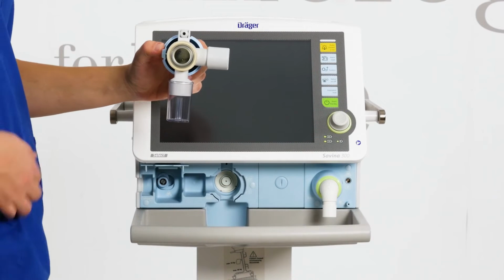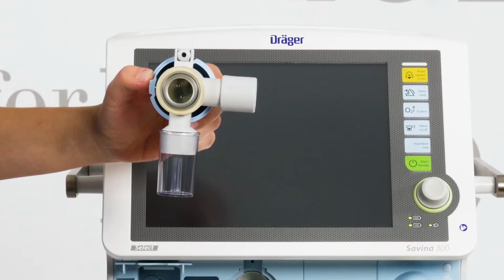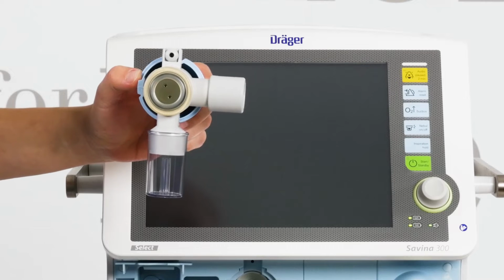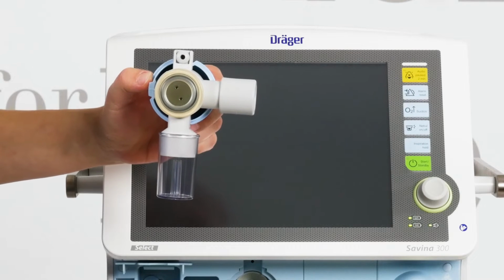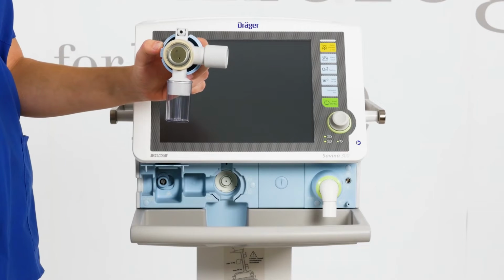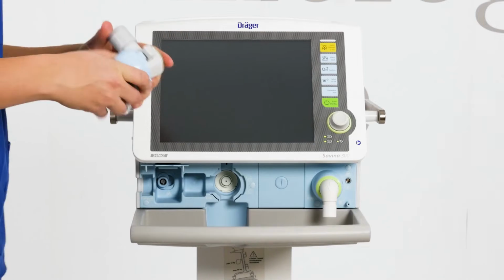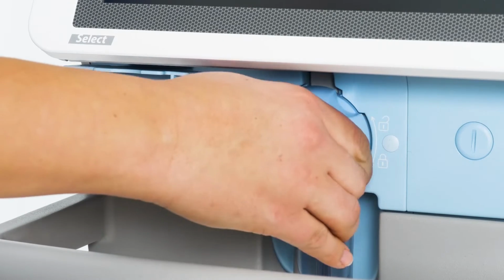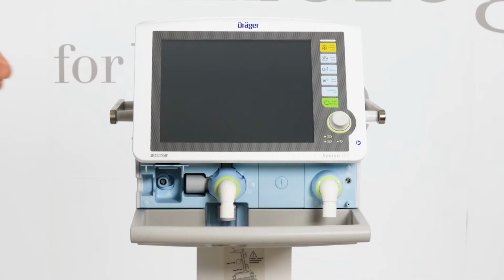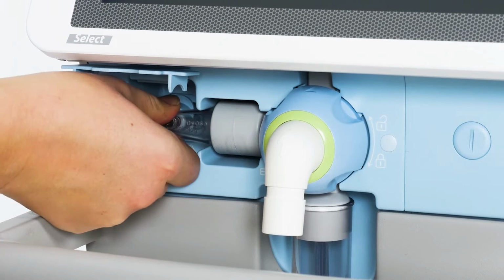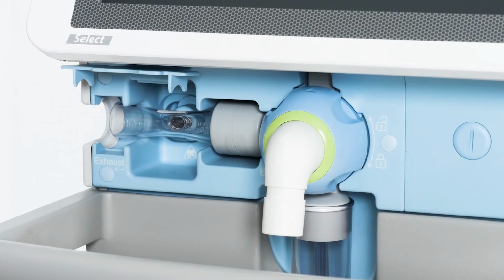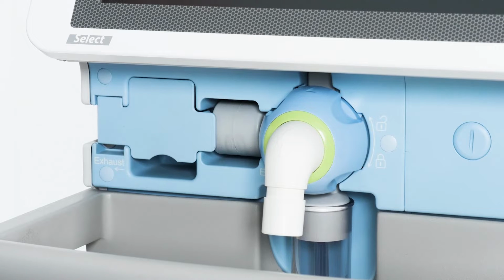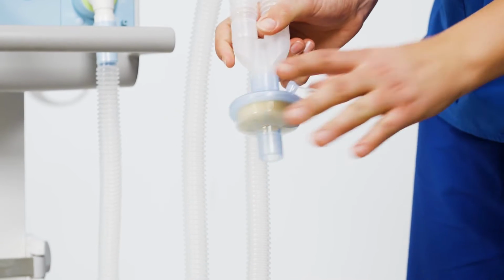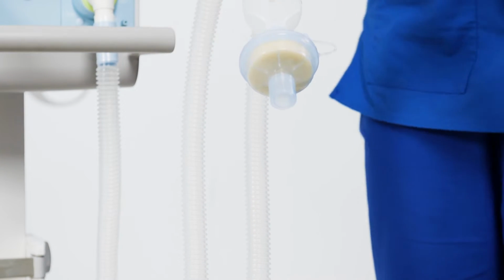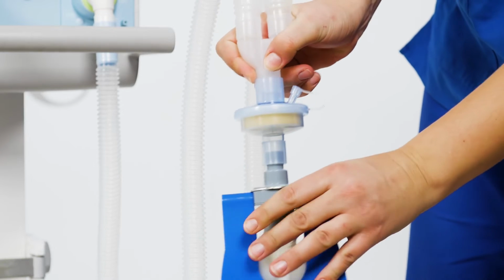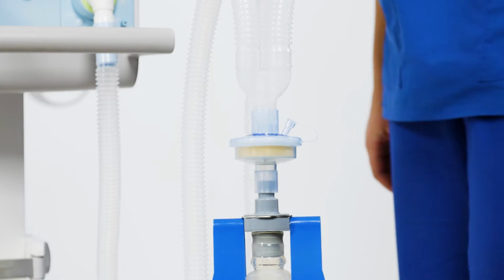Prepare the expiratory valve. Check that the diaphragm fits properly onto the edge of the expiratory valve housing and that the flow sensor sleeve and the water trap container have been attached. Then insert the expiratory valve. After that, insert the flow sensor and push it up to the stop in the flow sensor sleeve of the expiratory valve. If no breathing gas humidifier is used, we recommend the use of an inspiratory bacterial filter, HME, which has to be fitted onto the inspiratory port.